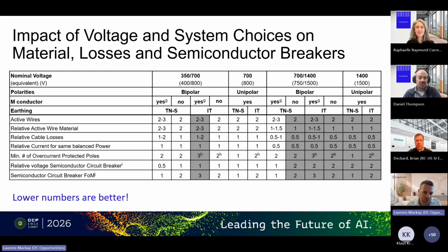And then these relative losses, it's very important there in where we have the 1 to 2, that is only in partial load you get a different percentage in losses, right? But effectively you still have lower losses because this unbalanced load we assume here you will only get if you have not full load. So you'll design your system for full load balanced operation, and then if it's unbalanced operation you get a bit different relative losses. Good.